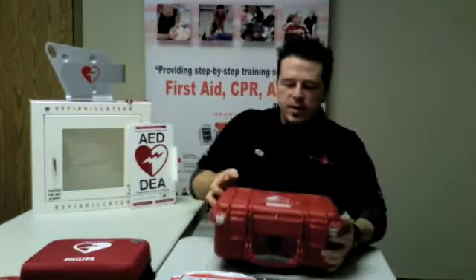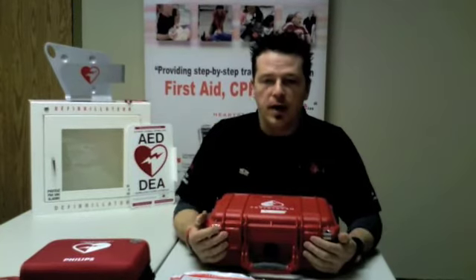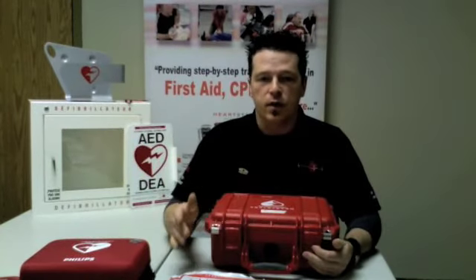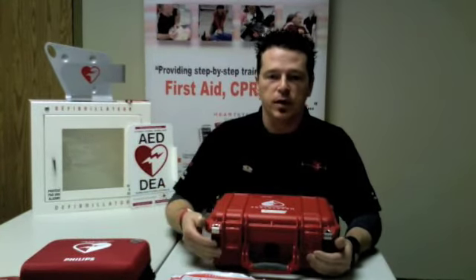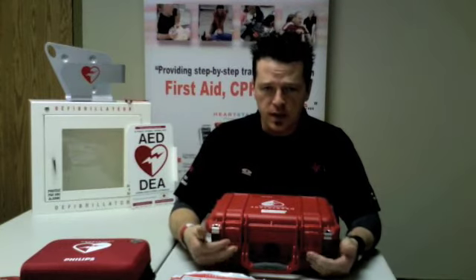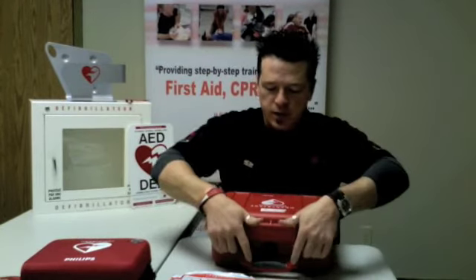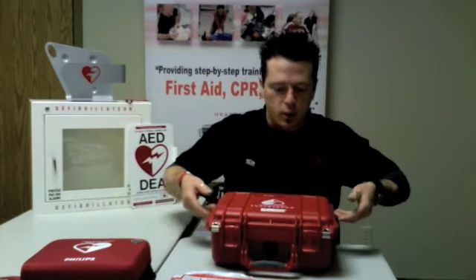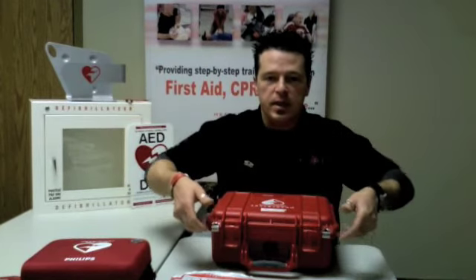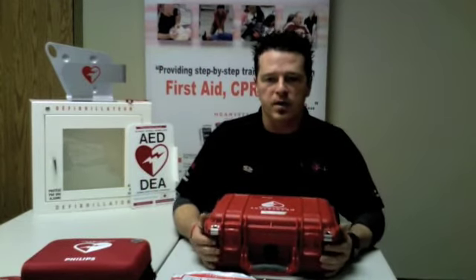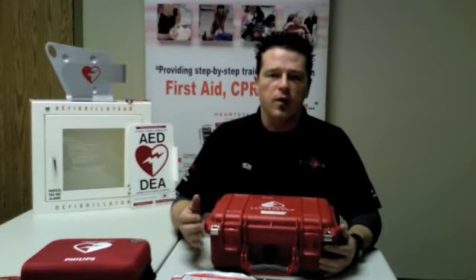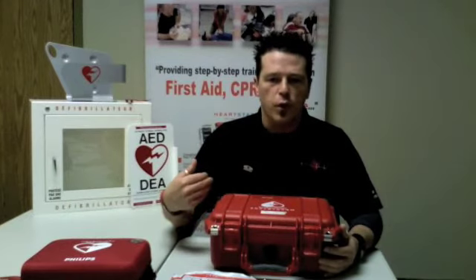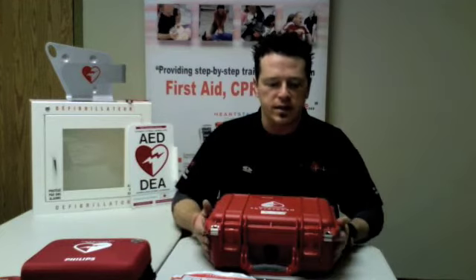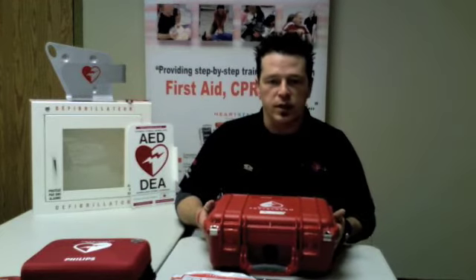If you're accessing the defibrillator through a Pelican hard case, the servicing is identical. It's just to access the defibrillator is a little bit different. Through these little casings here, these are actually making sure that there's a nice seal, waterproof, dustproof seal around the defibrillator, and these are typically used for sports teams, for fire departments, for construction sites that need a little bit more ruggedness to be affiliated with the protection of the defibrillator.